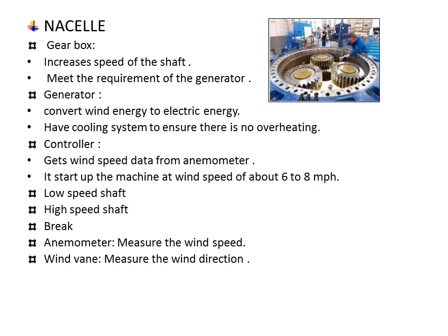The first one is the gearbox. The gearbox is used to change the low speed, high torque power coming from the blade to high speed, low torque power, which is used by the generator. It is connected between the main shaft and the generator shaft to increase the rotational speed from about 30 to 60 rpm to about 1000 to 1800 rpm. Gearboxes are made from superior quality aluminum alloys, stainless steel and cast iron.